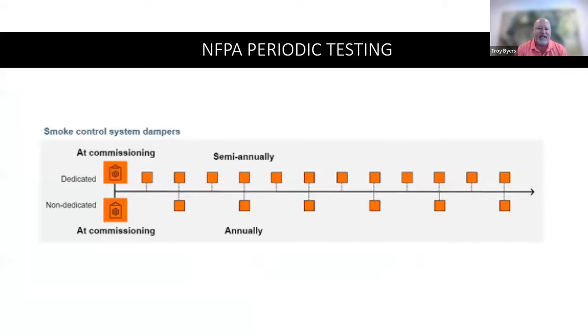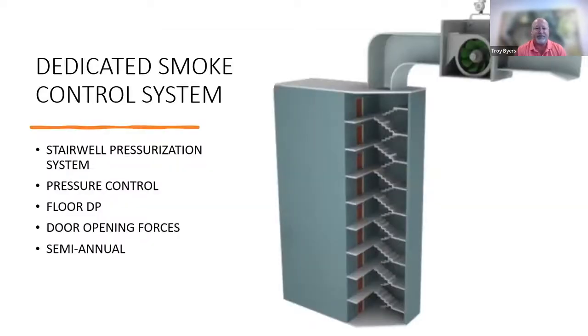What that means with regard to testing: for your dedicated system, at least for the system dampers, it's going to be at commissioning and then semi-annually, as Larry spelled out earlier, whereas the non-dedicated would be an annual test requirement. Let's look at some examples of a dedicated smoke control system. Here's one we would see for stairwell pressurization. If you're getting called to go out and test this system, whether new construction or existing, it's very important to understand the design, the sequence of operation, and the design intent.